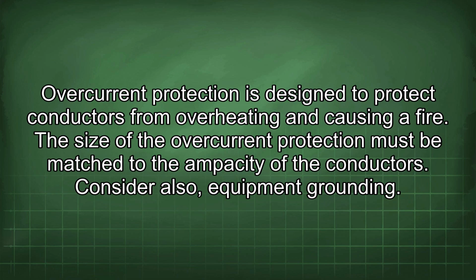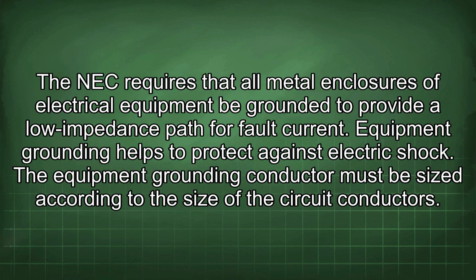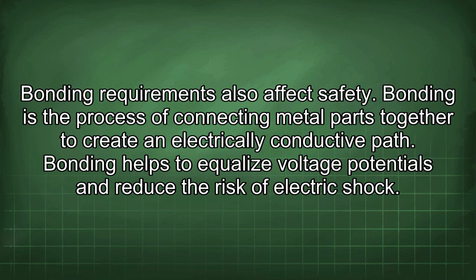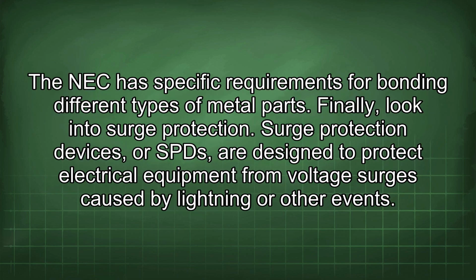Consider also equipment grounding. The NEC requires that all metal enclosures of electrical equipment be grounded to provide a low impedance path for fault current. Equipment grounding helps to protect against electric shock. The equipment grounding conductor must be sized according to the size of the circuit conductors. Bonding requirements also affect safety. Bonding is the process of connecting metal parts together to create an electrically conductive path. Bonding helps to equalize voltage potentials and reduce the risk of electric shock. The NEC has specific requirements for bonding different types of metal parts.